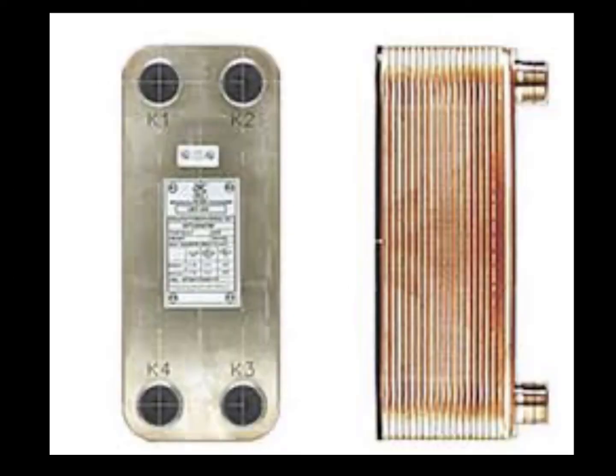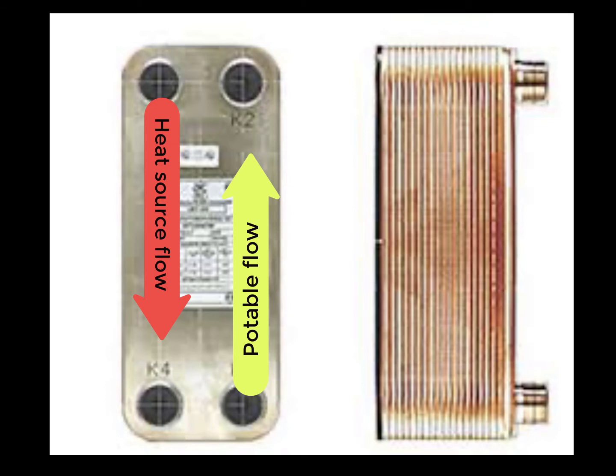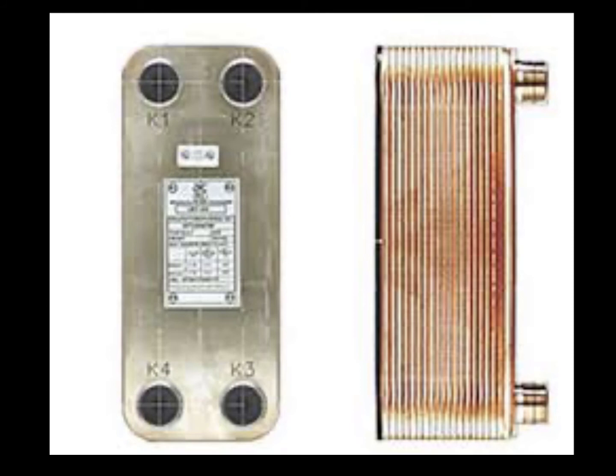Now showing on the screen is a flat plate heat exchanger, also known as brazed plate. Although this is a very efficient method of heat transfer, its transfer efficiency is based on the fact that it has significant surface area for the heat exchanger surfaces themselves. It is important that the fluids be counterflowed. In other words, your potable water needs to go through this in the opposite direction as your heat source water. And it also is complicated by the fact that it requires a secondary pump to extract heat from the heat exchanger and transfer it into the storage tank. These are not very common, but it is one method of domestic hot water heating that can work rather efficiently.